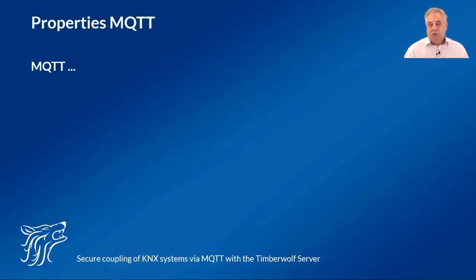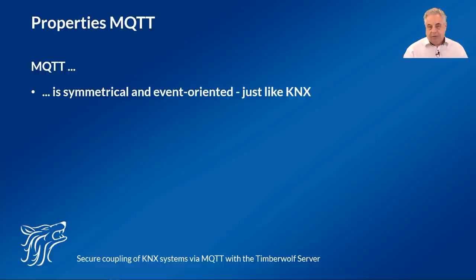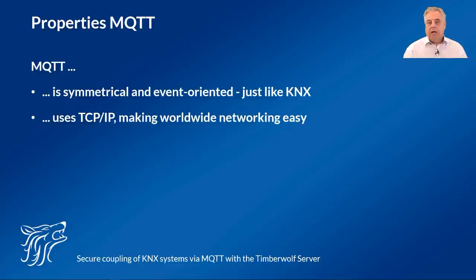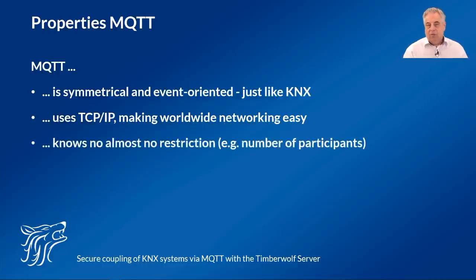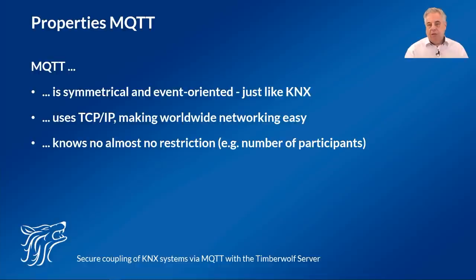Let's take a brief look at the properties of MQTT. The protocol is symmetrical and event-oriented, just like KNX. MQTT uses TCP, so worldwide networking via IP networks is really easy. The number of participants is arbitrary, a maximum bandwidth is not specified, and it works well even over poor connections — up to 256 MB can be transferred with a single message. In practice, performance depends on the respective clients, the broker, and the IP networks. HiveMQ's MQTT broker achieved a throughput of 3 billion messages per hour in a test with 10 million MQTT clients.